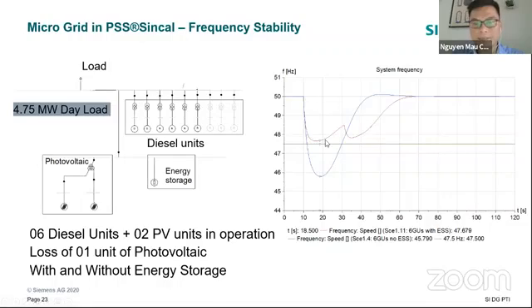At this moment the energy storage discharges active power to keep the frequency above the limit. Then the energy storage runs out of charge, they use all the energy, and start to recharge. That's why when they start recharging, the frequency goes down, because the energy storage takes power from the system and consumes active power. But at the end, the frequency comes back to 50 hertz and stabilizes.